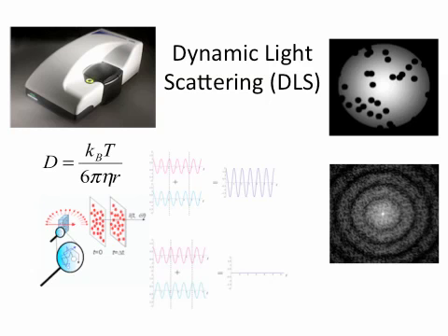Typically, there are a number of manufacturers. The picture here at the top is a Malvern Nanosizer in this particular case. What you do is disperse your particles inside a cuvette and hit it with a laser beam, as depicted over here. As a result, you get a scattering profile. One of the pictures is given here on this side. Then what you basically do is take pictures at different time points. I'll go through it a little bit to explain how you go from this picture to an average size. So how does it work?